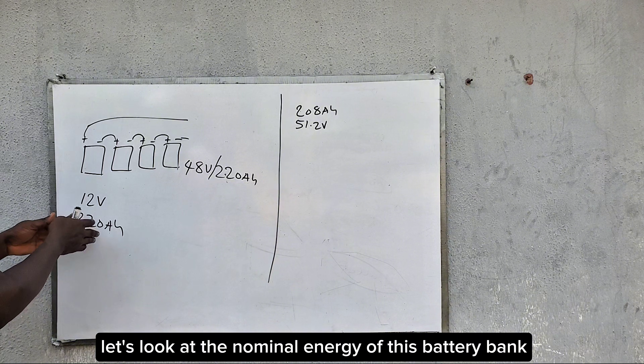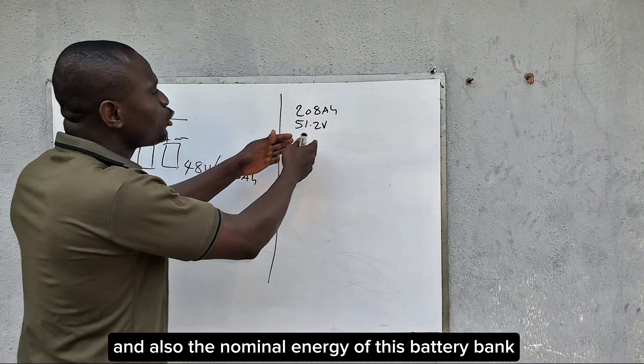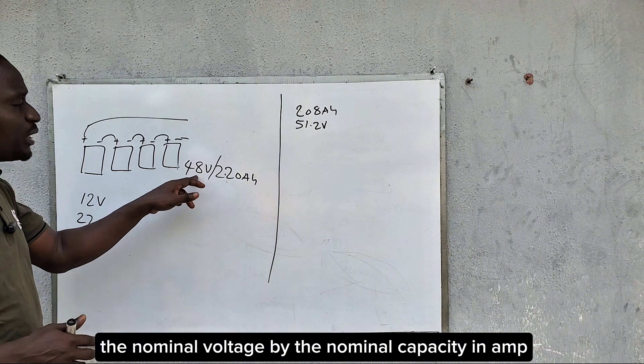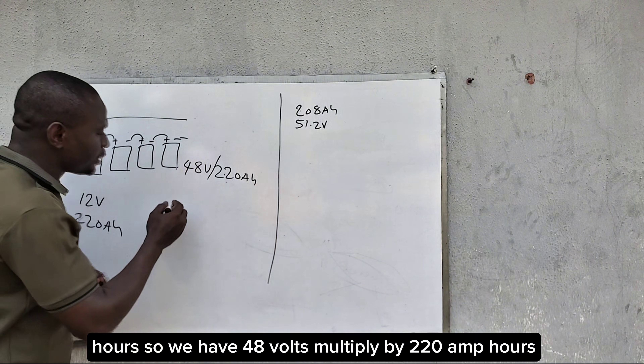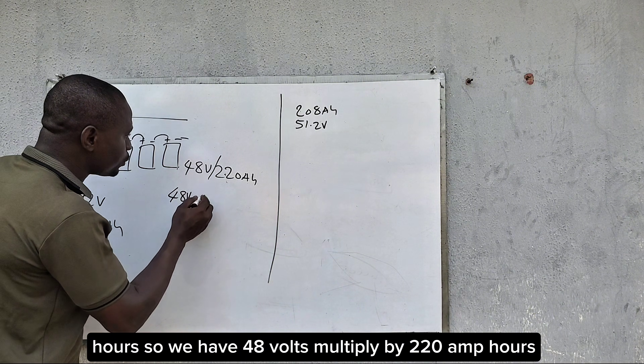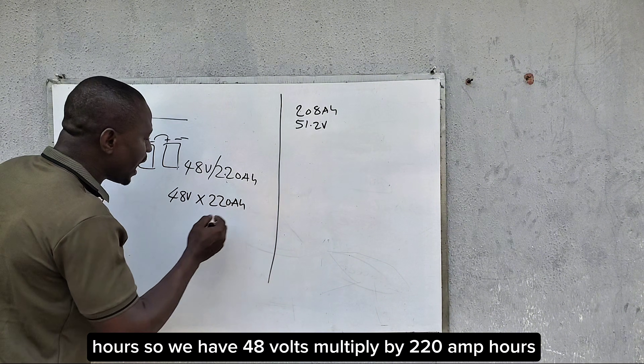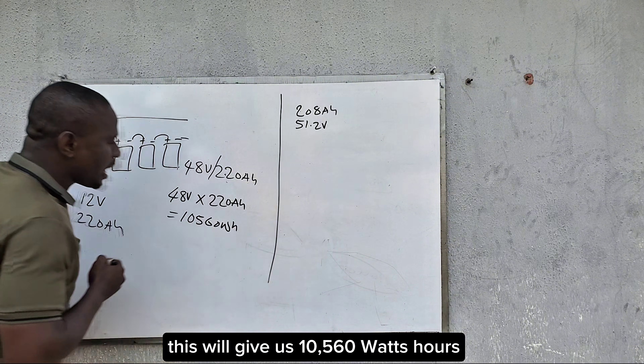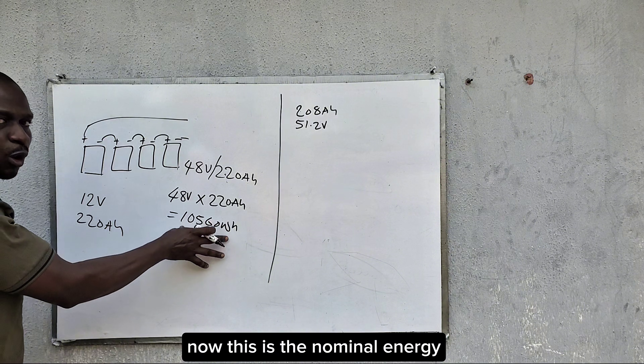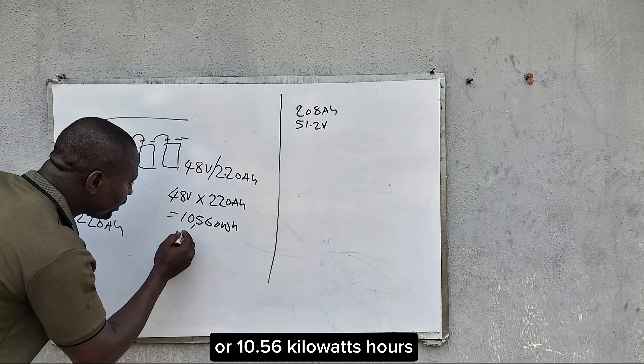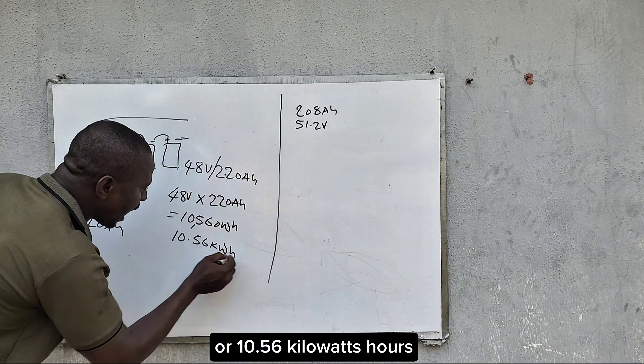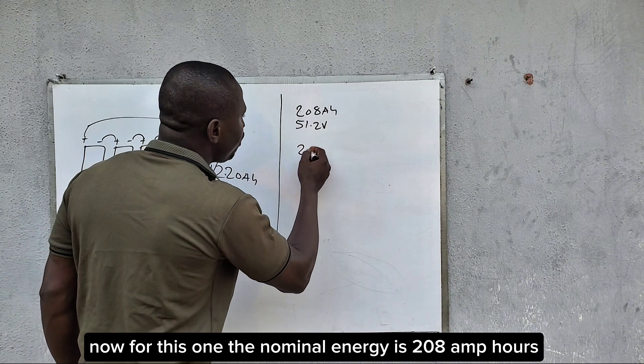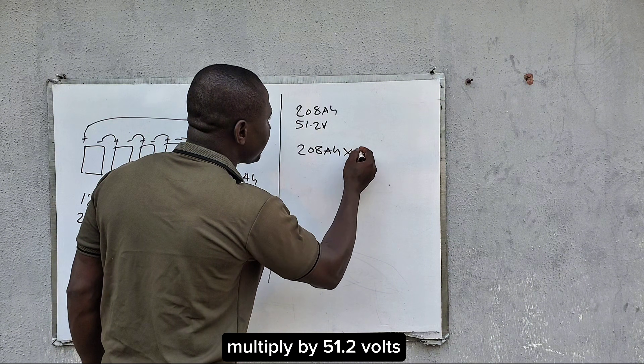Now let's look at the nominal energy of each battery bank. To calculate nominal energy, we multiply the nominal voltage by the nominal capacity in amp hours. For the tubular battery bank: 48 volts multiplied by 220 amp hours gives us 10,560 watt hours, which is 10.56 kilowatt hours.